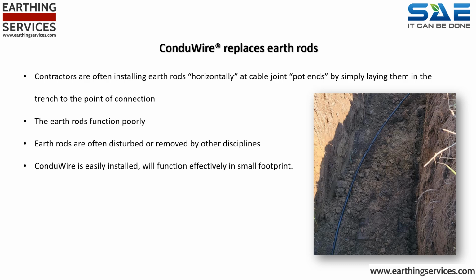ConduWire can be used for LV and HV systems. In respect of LV work, contractors are often installing earth rods horizontally at cable joint pot ends, simply by laying them in the trench to the point of connection. The earth rods function poorly. Earth rods are often disturbed or removed by other disciplines. ConduWire is easily installed and will function effectively in a small footprint.